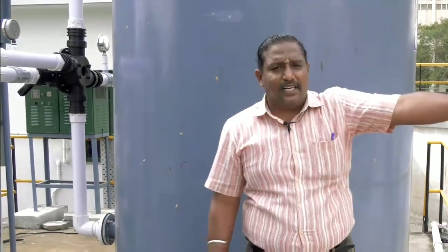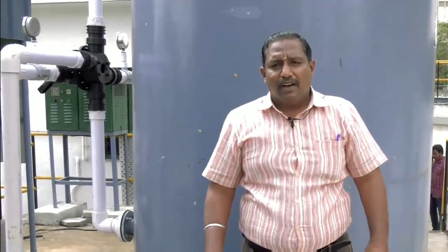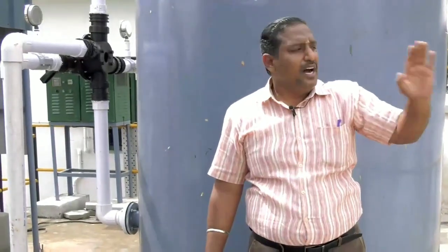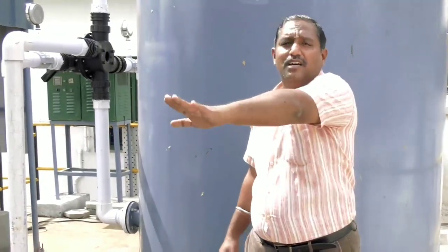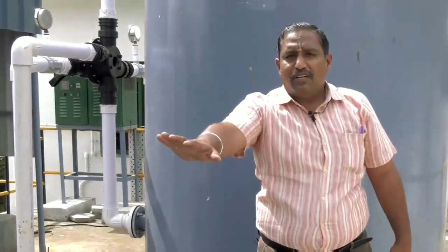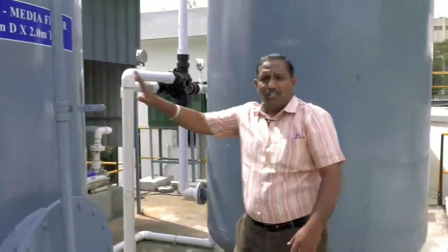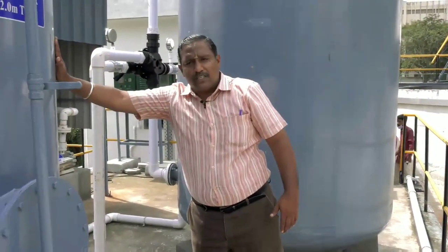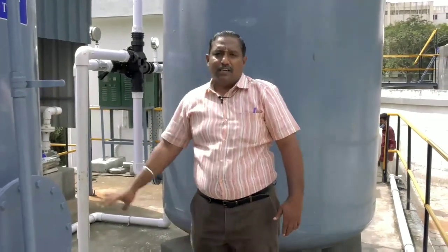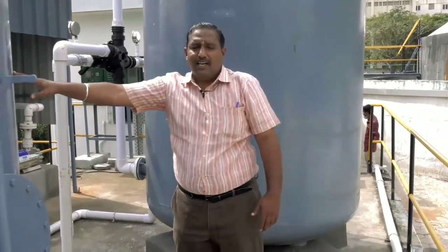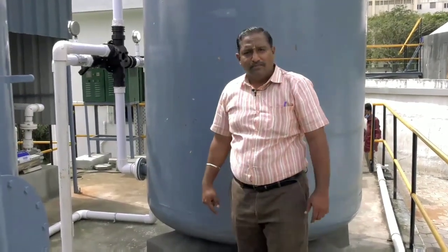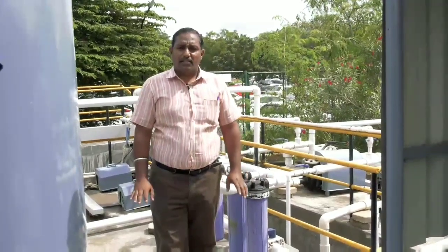After the aerobic system, it enters the clarifier, where the biosolids, the biomass or biological sludge, are separated from the water, and the supernatant clear water is taken to the filter feed sump. From the filter feed sump, it is once again pumped into the polishing cylinders, where further suspended solids are removed with the help of the multimedia filter, and the color is removed with the help of the activated carbon filter. So now we are seeing the final stage of treatment.